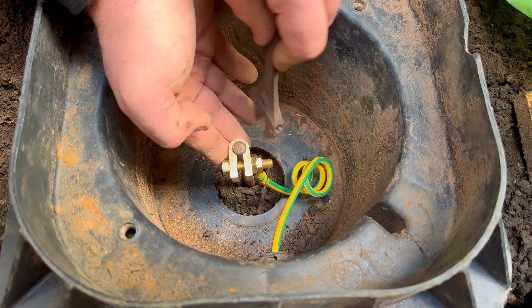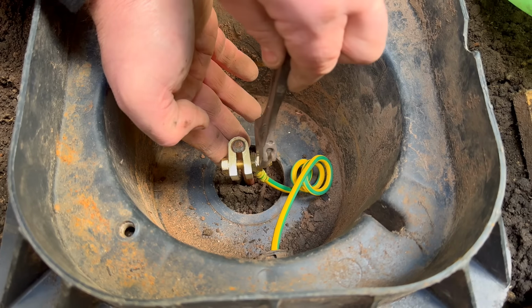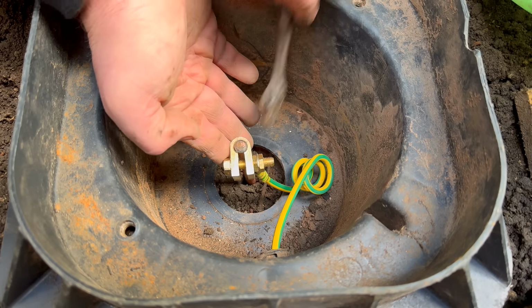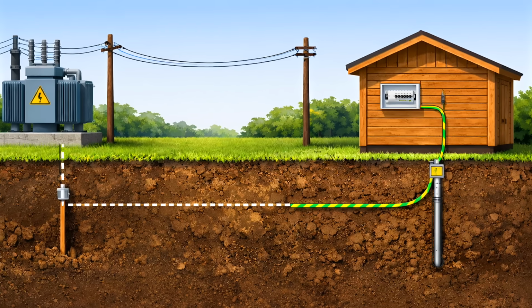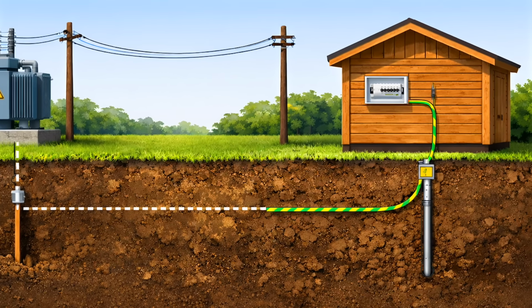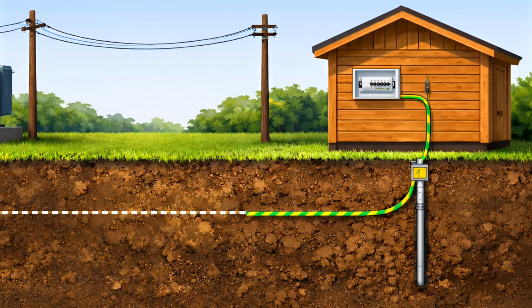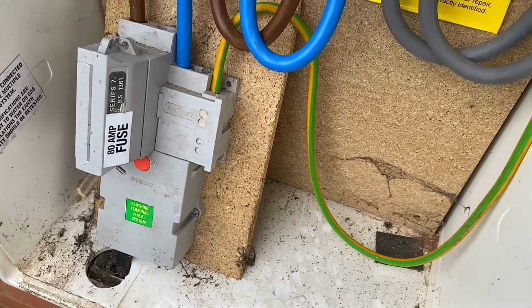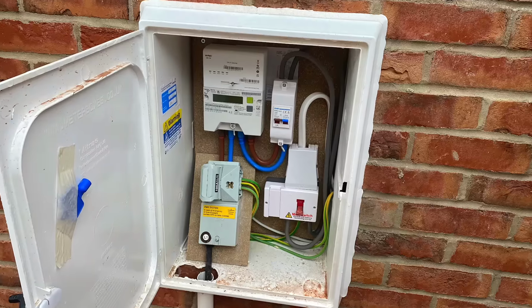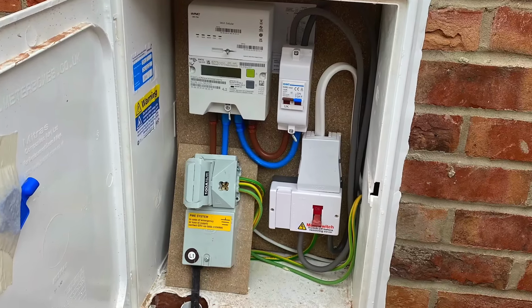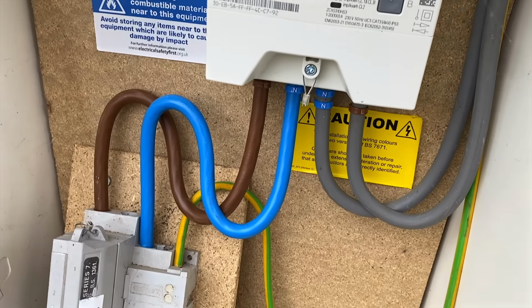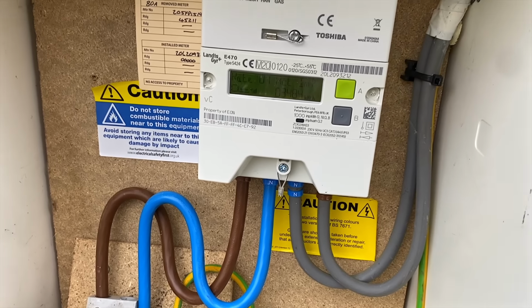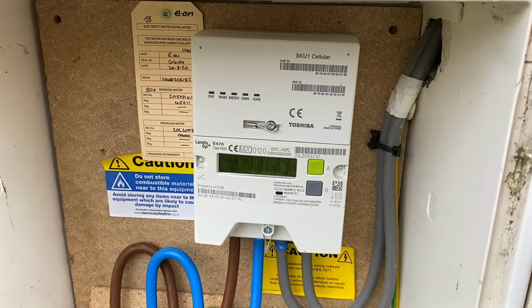Before we get into testing, it's worth reminding ourselves why we use earth electrodes in the first place. It provides a local connection to earth so that fault current has a controlled path away from exposed conductive parts. In a TT system, that earth electrode is the only intentional connection between the installation and the ground. And that matters because not every earthing system behaves the same way. On TN systems, the earth is provided by the supply network. On TNCS systems in particular, earth and neutral are combined in the network and separated at the point of supply.